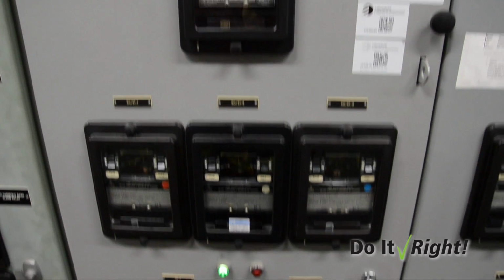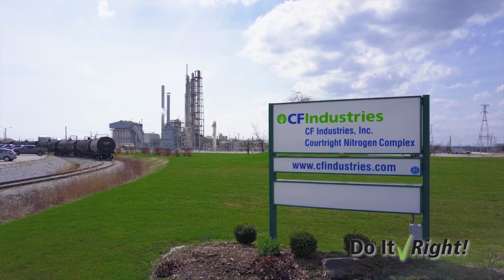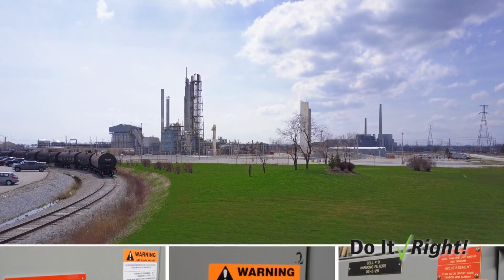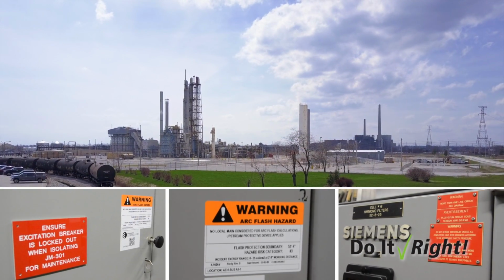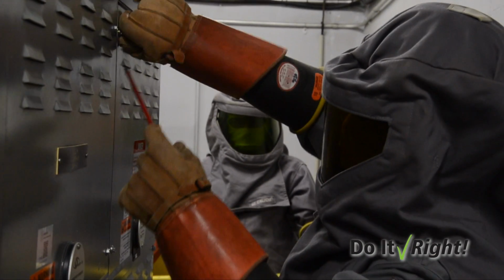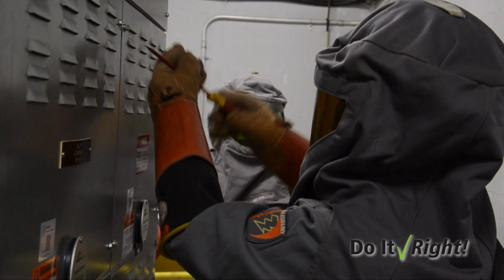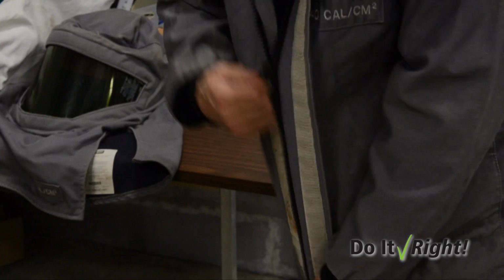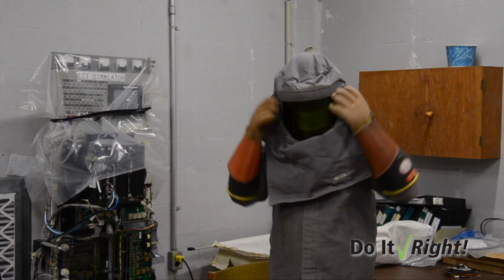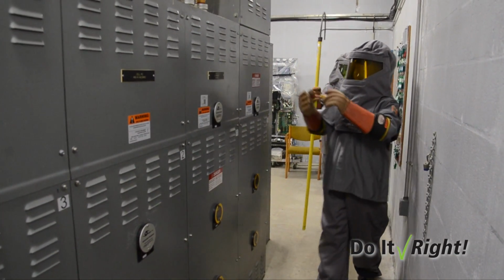The purpose of the scan is to determine faults early so that we can go shut down equipment, repair it before we have a failure. Failure can lead to electrical fires or unplanned unit shutdowns or potential for a fatality. Before, you would take the panel off the live electrical equipment. The arc flash suit was at least providing you some protection against the heat, but it doesn't protect you really much against the explosive impact.